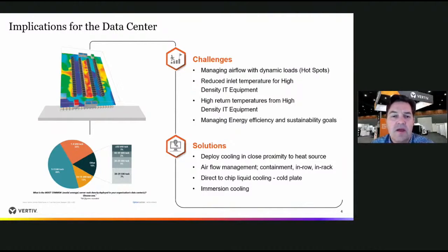The key to the strategy is to deploy cooling in close proximity to the heat source. Airflow management, containment, and in-row and in-rack solutions allow cooling to get closer to the source of heat. New and exciting technologies such as direct-to-chip liquid cooling using cold plates or immersion cooling are becoming mainstream offerings, with increased offerings from the industry, including server OEM manufacturers and large vendors such as Intel, who are delivering these solutions and ensuring the infrastructure is there to support them. As an industry throughout India, we're seeing these technologies adopted in exciting new ways, and I'll share a roadmap of how this can scale.